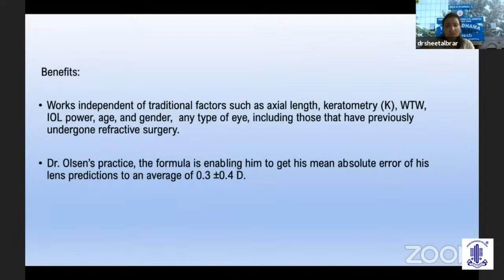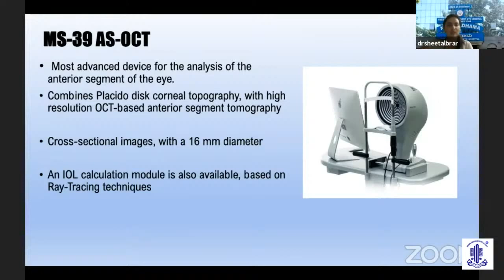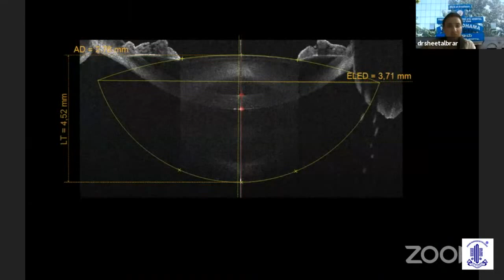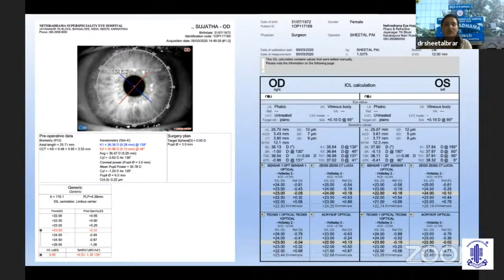So another equipment which uses ray tracing technology is the MS39 AS-OCT. It is the most advanced device for the analysis of the anterior segment of the eye. It combines Placido disc topography with high resolution OCT to give high resolution anterior segment tomography cross-sectional images over a span of 16 millimeters corneal diameter. This machine also has an IOL calculation module available inside, which is based on ray tracing techniques, and this also measures the lens thickness. And we are using this formula and this technology for post-refractive surgery eyes. What we are seeing is that the predictability of ray tracing technology in this scenario is very similar to the gold standard Barrett TrueK formula and also the Barrett TK, which I'll be talking about later.